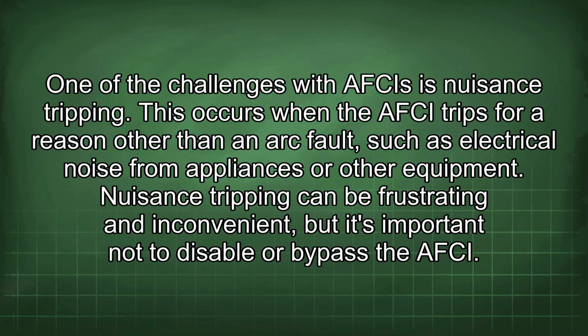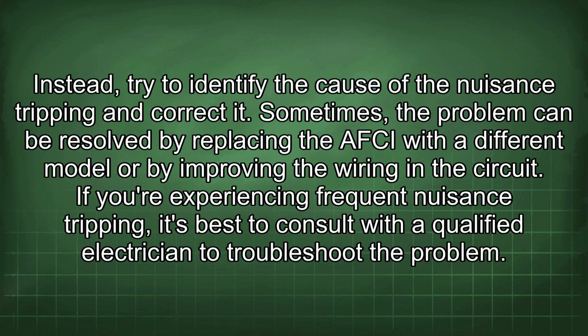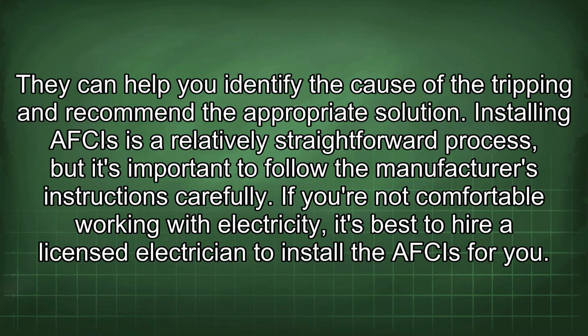This occurs when the AFCI trips for a reason other than an arc fault, such as electrical noise from appliances or other equipment. Nuisance tripping can be frustrating and inconvenient, but it's important not to disable or bypass the AFCI. Instead, try to identify the cause of the nuisance tripping and correct it. Sometimes, the problem can be resolved by replacing the AFCI with a different model or by improving the wiring in the circuit. If you're experiencing frequent nuisance tripping, it's best to consult with a qualified electrician to troubleshoot the problem. They can help you identify the cause of the tripping and recommend the appropriate solution.